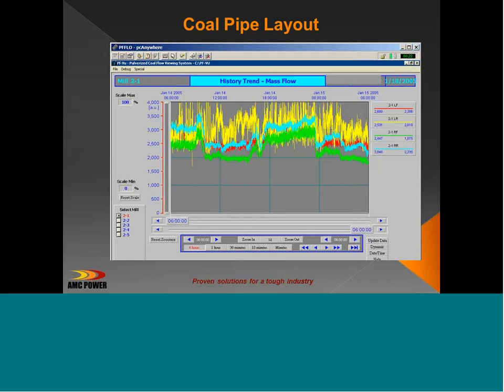It tells us a lot about how the fuel is being delivered, how smoothly that fuel is being delivered to the burner. And in this case, we can see the yellow pipe, which is heavily loaded, is not very smooth. It's what we call slugging. You've got coal laying out and blowing and laying out and blowing. And again, this is a 24-hour window, so you're seeing it through a variety of mill load changes.